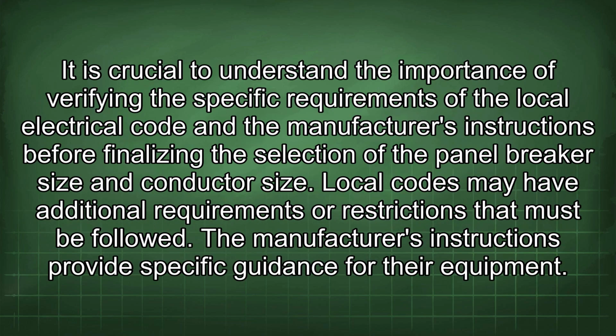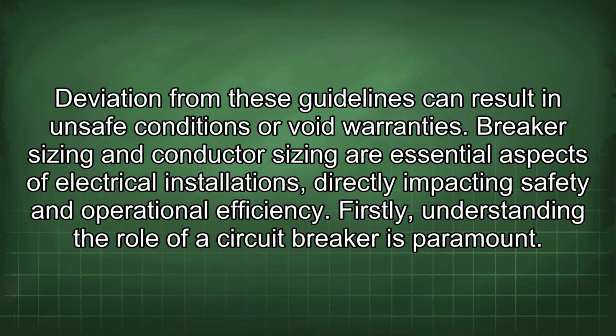It is crucial to understand the importance of verifying the specific requirements of the local electrical code and the manufacturer's instructions before finalizing the selection of the panel breaker size and conductor size. Local codes may have additional requirements or restrictions that must be followed. The manufacturer's instructions provide specific guidance for their equipment. Deviation from these guidelines can result in unsafe conditions or void warranties.